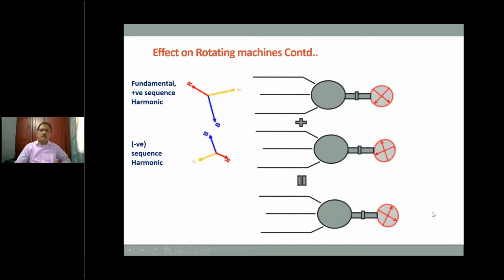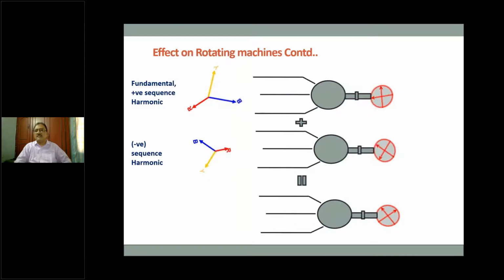Some of you who must have listened to me on the previous 2 occasions will remember that I repeatedly used the phrase that motors deliver what the load demands. So when the whole job of a motor is to deliver what is demanded by the load, the motor will make additional efforts and take more power to meet the demand from the load. Therefore, the motor will run very, very hot. So this is another way to find out how the harmonic is affecting your rotating electrical system.